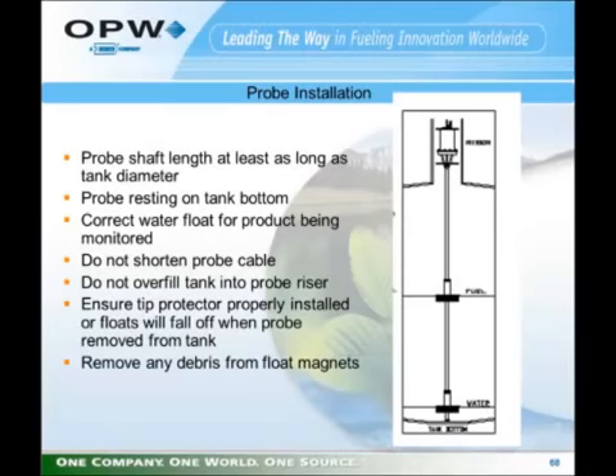The probe shaft should be at least as long as the tank diameter. The probe must rest on the bottom of the tank. It cannot be suspended in the tank. The correct water float must be used. We don't recommend that you shorten the probe cable. Do not overfill the tank into the probe riser. Should you overfill the tank into the probe riser, there is a possibility that product will enter into the head of the probe. If product enters into the head of the probe, it will damage the probe.